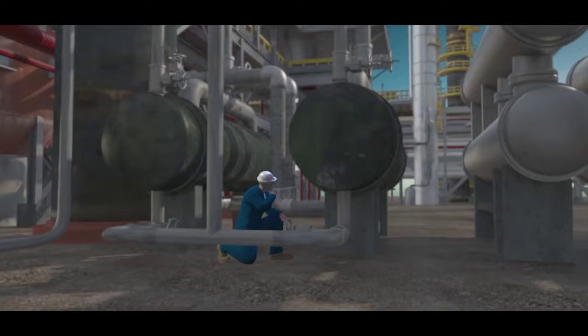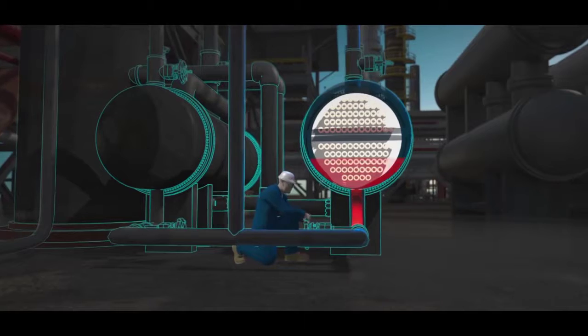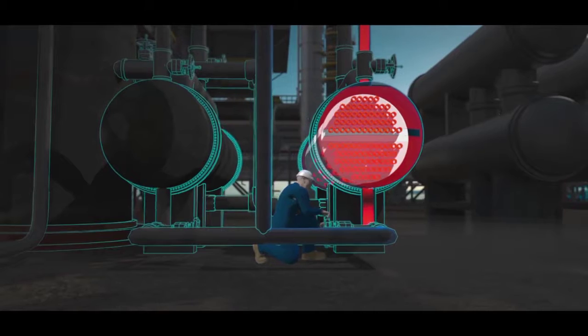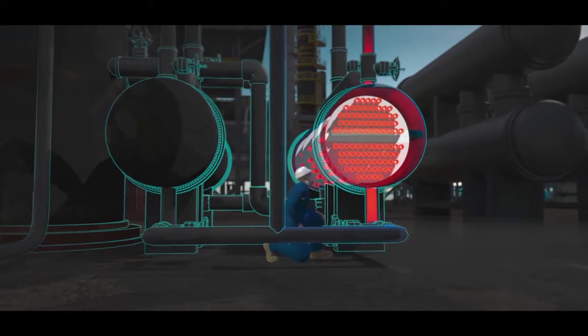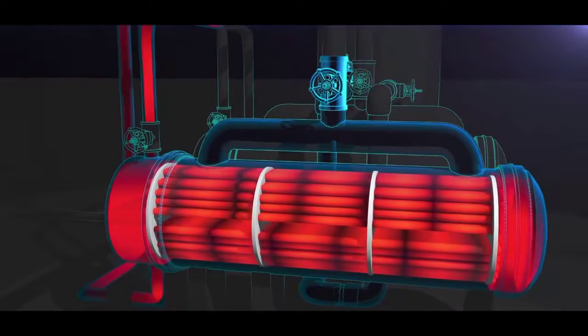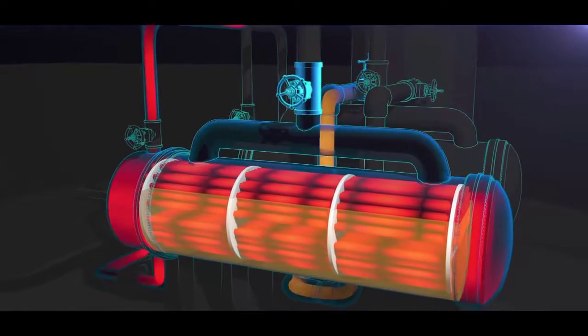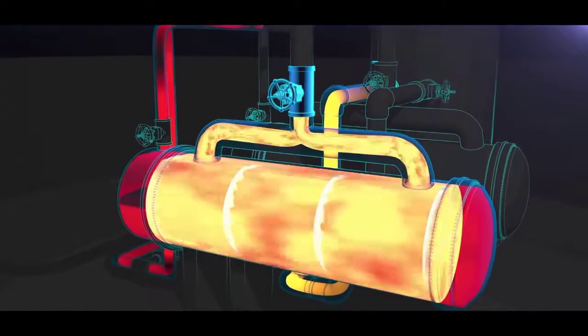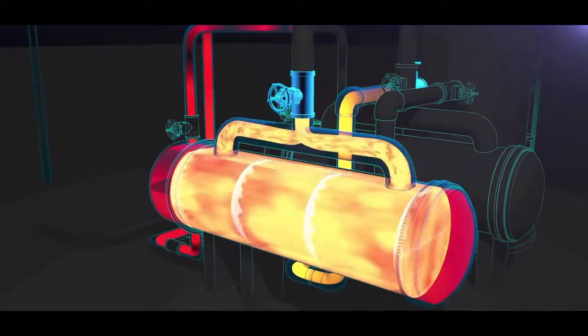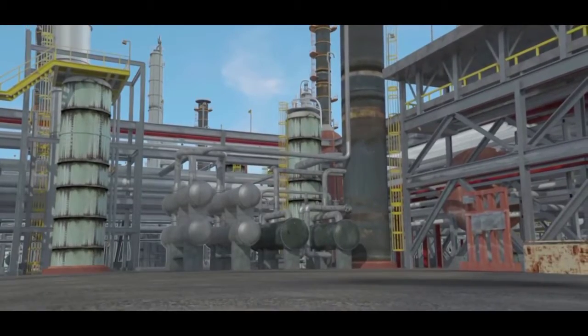The CSB determined that at 8:33 a.m., the operations supervisor likely opened the water valves on the standby reboiler. Hot water began flowing inside. The valves blocking the reboiler from its protective pressure relief valve remained closed. But unknown to the operations supervisor, the standby reboiler contained flammable liquid propane that had accumulated during the 16 months the reboiler was out of service. The hot water quickly heated the liquid propane confined inside of the reboiler, and pressure dangerously increased. Just 3 minutes later, the reboiler violently ruptured.